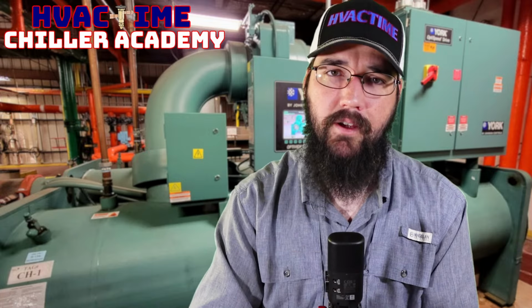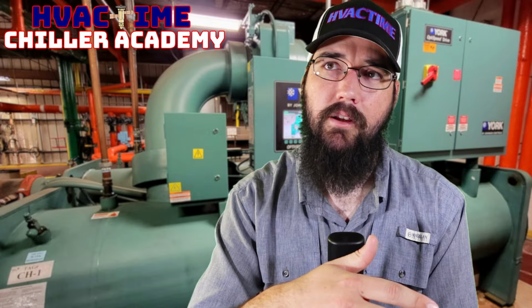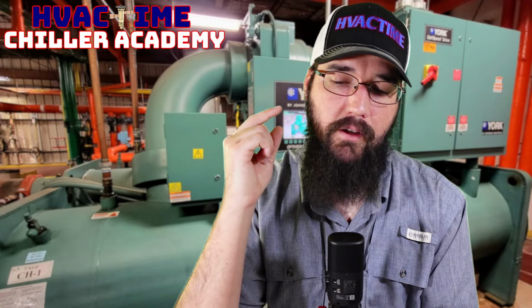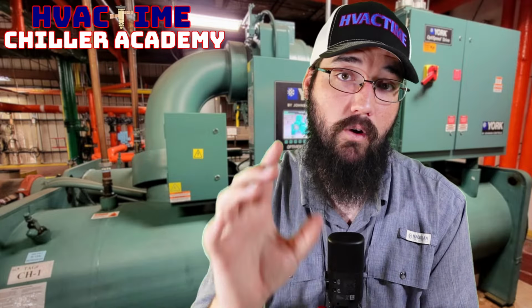And then instead of CFM, cubic feet per minute, or if you're doing CLM, cubic liters per minute, whatever the metric version of that is, we're now dealing with GPM, which is gallons per minute, and then convert that to whatever metric version that is if you need to. But that's the core difference, right? So if you can think about water flow the same way you already think about airflow, you've now got a core grasp of how the water flow works. Everything else stays basically the same. It's all the same principles. How you would troubleshoot low airflow, you're going to troubleshoot low water flow.